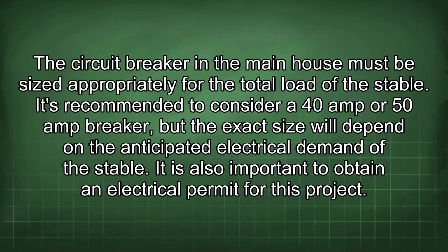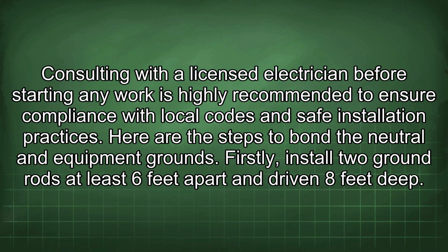The circuit breaker in the main house must be sized appropriately for the total load of the stable. It's recommended to consider a 40 amp or 50 amp breaker, but the exact size will depend on the anticipated electrical demand of the stable. It is also important to obtain an electrical permit for this project. Consulting with a licensed electrician before starting any work is highly recommended to ensure compliance with local codes and safe installation practices.